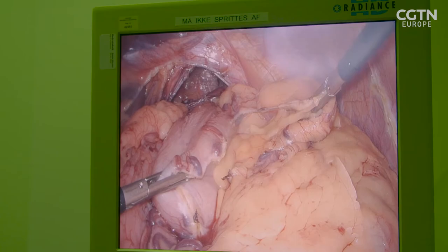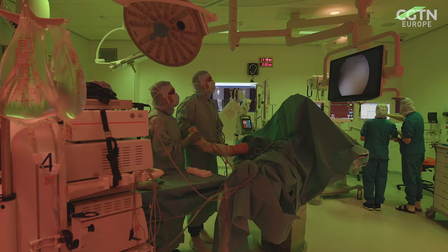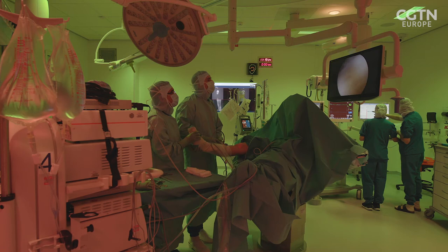Your eyes and brain are not having to work as hard as they might have in an old surgery with lots of white light. Having the red light behind the surgeon — which is the same color spectrum as the images on screen — also reduces reflections. And if you have a room that is monotone green throughout, that's not a nice place for supporting staff. But if you have the complementary colors represented with green on one side and red on the other, you build up a balance and harmony in the room.